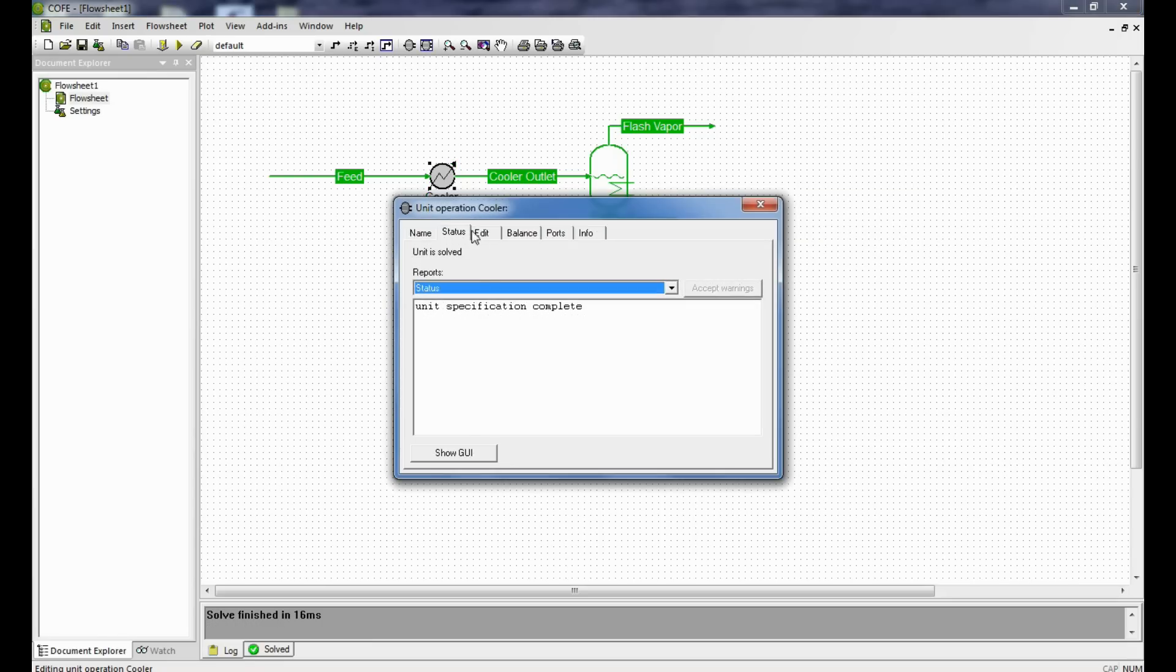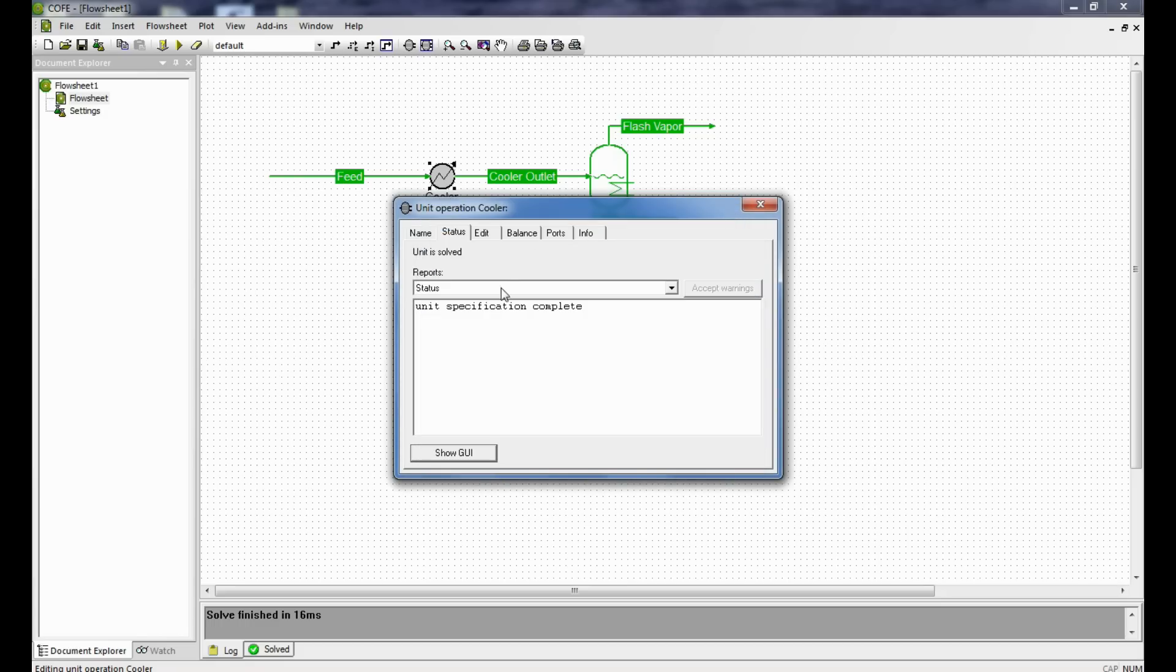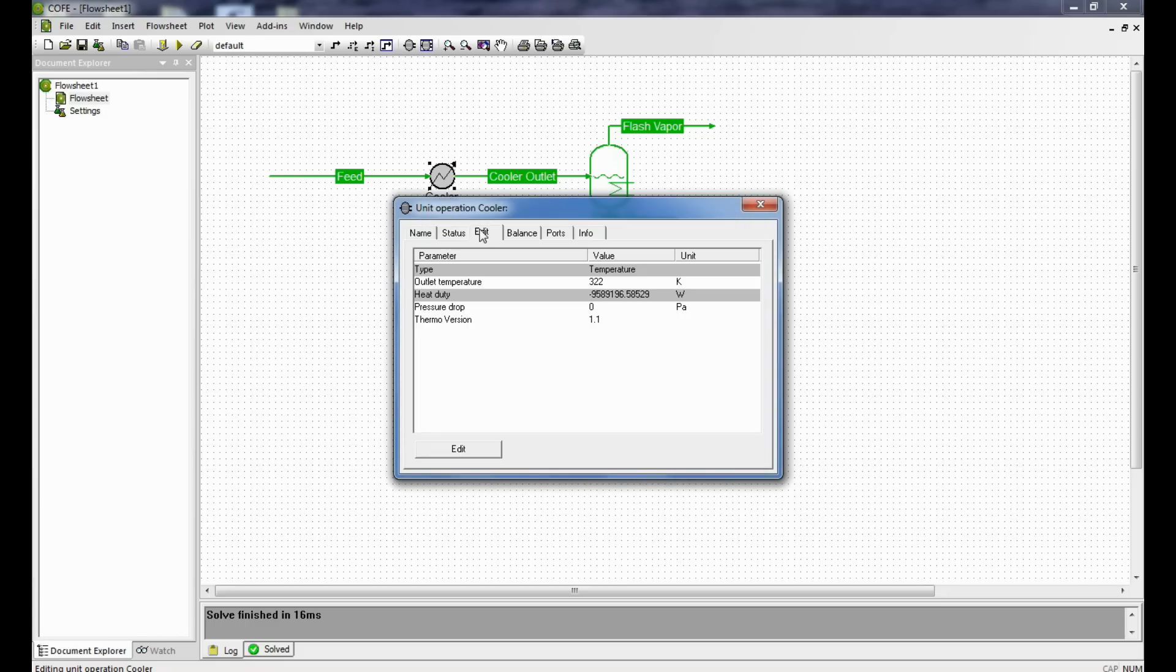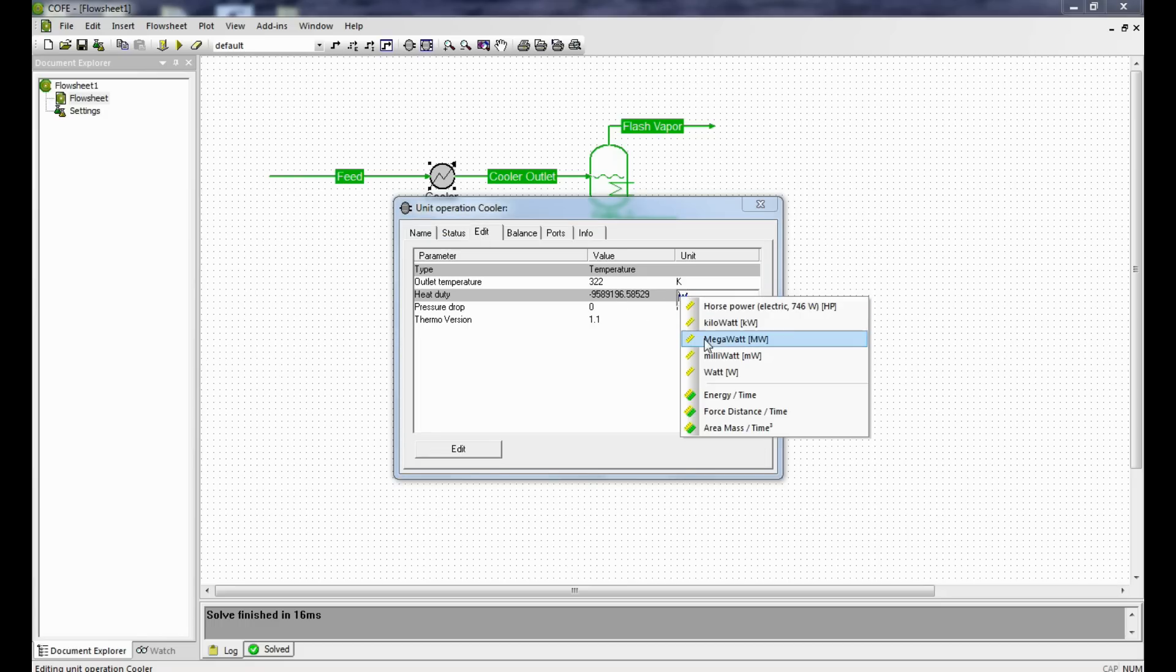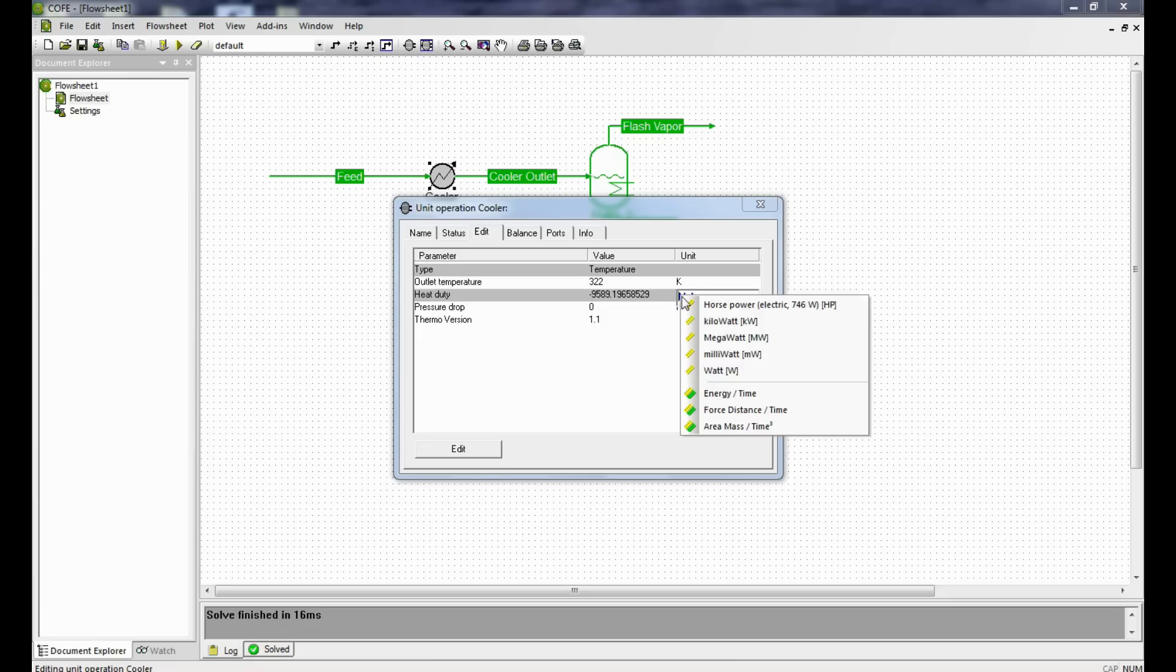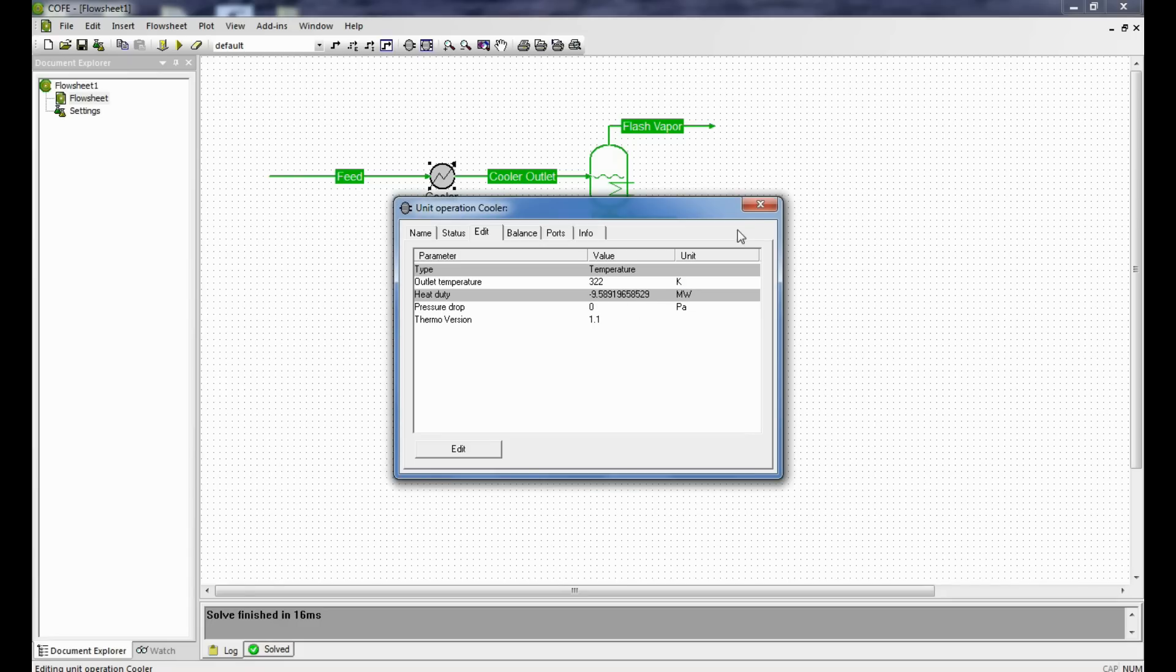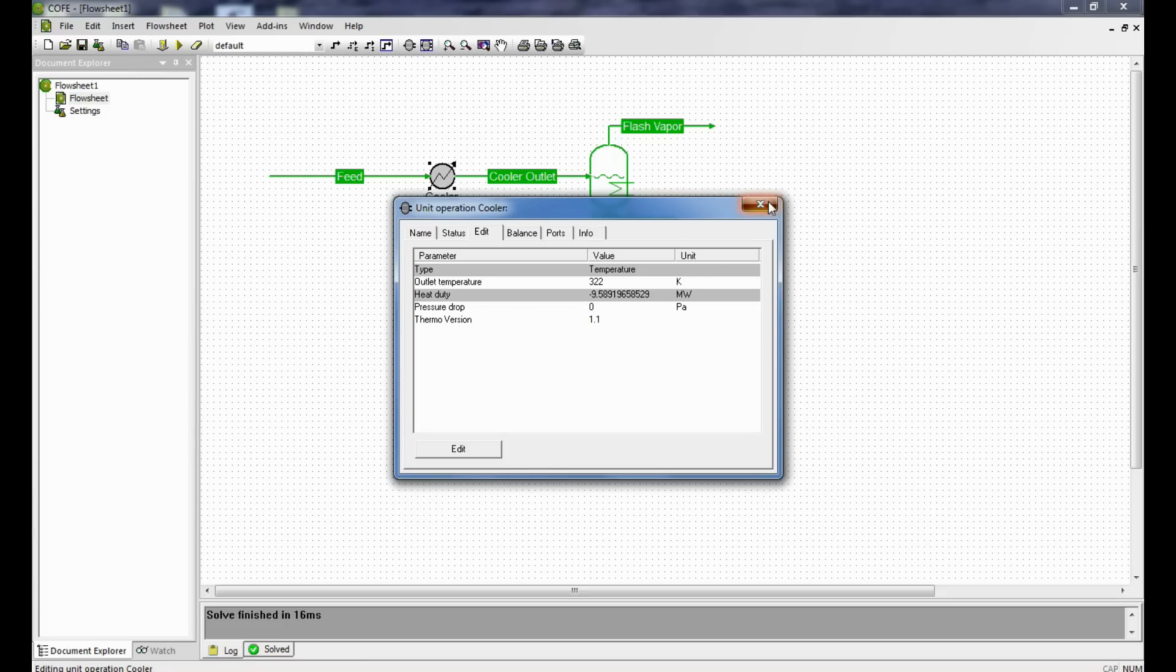Now the load here in the exchanger, the load in the exchanger is minus 9.5891 megawatts. The minus sign indicates that the heat has to be removed. Let's keep a note of this figure, minus 9.5891 megawatts.